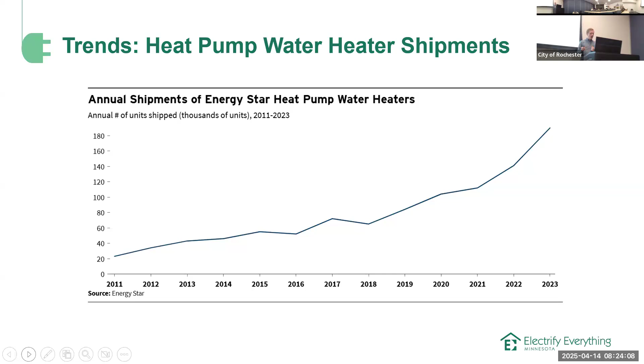Another trend supporting the growth of heat pump water heater adoption is the Department of Energy's finalization last year of efficiency standards for water heaters, promoted as a way to save Americans over $7 billion on energy bills. What this means is that starting in 2029, about 50% of water heaters manufactured will be required to meet efficiency standards that only heat pump water heaters can meet. So basically, in 2029, 50% of electric water heaters manufactured and installed in the United States will be heat pump water heaters. I know Haley and Tana are both leaders in the Rochester area on heat pump water heaters, so you're setting yourselves up really well to meet this trend leading to 2029.